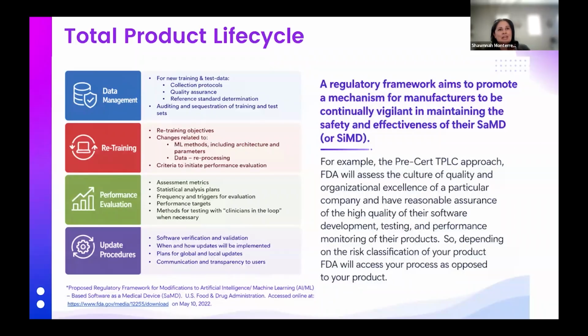Understanding that the software has changed, reprocessing, rechecking performance, making sure that as you're retraining the algorithm, you're still meeting essential performance. Performance evaluation goes part and parcel with that. And then just making sure that you have updated procedures on how you actually perform the updates. Are you organically retraining the algorithm? Do you have a process and control in place to actually QC the data coming in to retrain the algorithm? Do you have something in place to revalidate the algorithm to make sure it's still performing as expected? These are things that are part of the total product life cycle.